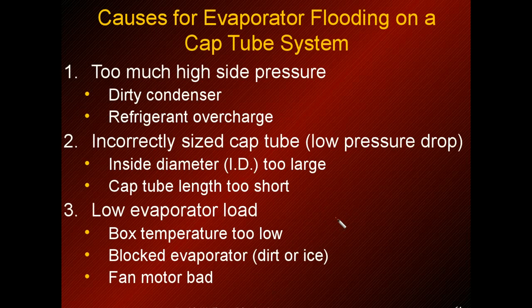If a cap tube system is flooding, here are some causes. When working on a cap tube system, avoid putting your gauges on if possible, because when you remove them you lose refrigerant, and there's so little refrigerant that it can affect the system quite a bit. If you have too high-side pressure, look for a dirty condenser or a possible refrigerant overcharge. An incorrectly sized cap tube is another cause, most likely if someone recently replaced it. Low evaporator load can result from a dirty or iced evaporator, bad fan motor, or very low box temperature.